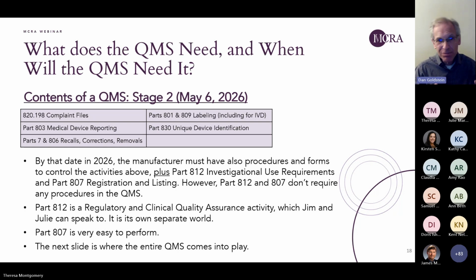And because Part 801 calls out Part 830, which is for unique device identification, those barcodes or QR codes that you now have on every medical device, that's going to have to be followed as well. And again, the manufacturer will have to have procedures that say, here's how we do labeling, including, if necessary, here's how we create UDI codes. So that's all going to be in place as well.